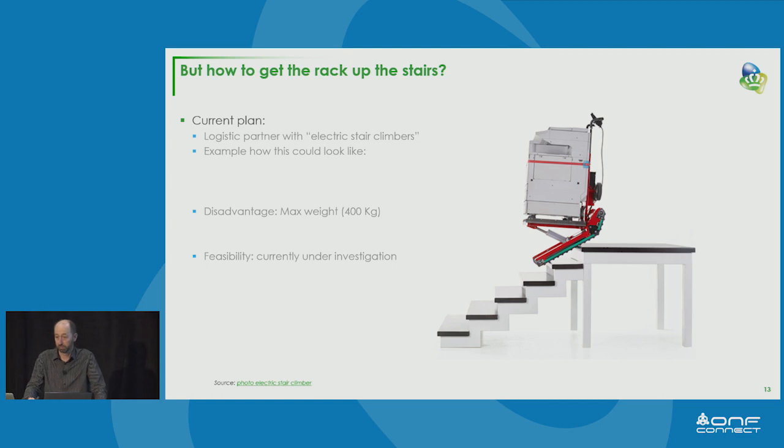They have a max weight of something like 400 kilos, but again, in our central offices, instead of putting a lot of servers in, we'll probably put in a lot of switches. And then not only does the power consumption go down compared to the hyperscaler server setup, but also the weight will go down. So we did some calculations, and it seems like the 400 kilos will actually fit. So this is something we are currently investigating. If they explore this a bit further, this seems a way to tackle the staircase challenge.